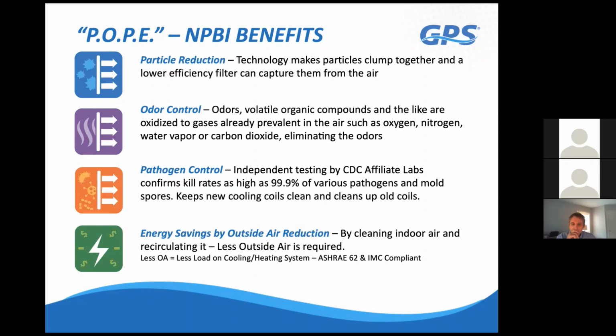We control odors through oxidation. We break down these gases and odors in the airstream by imparting a certain electron volt potential into the air. We use 12 electron volts. That's no secret with our technology. That's just below oxygen, so we don't generate that ozone. And we convert these contaminants with electron volt potentials of less than 12 back to what's prevalent in the atmosphere: oxygen, nitrogen, water vapor, carbon dioxide.